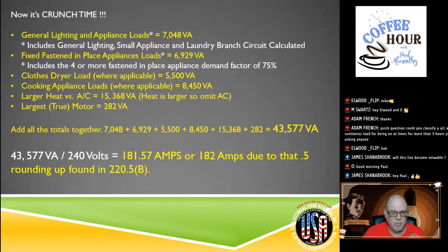All right, so we did this one. So now it's a 220-240 volt service, single phase. So 43,577 divided by 240 gives us 181.57. Again, 0.5, we're going to round, so we have 182 amps. And again, due to that 0.5, that's how we round it up. So that's our size, 182 amps.